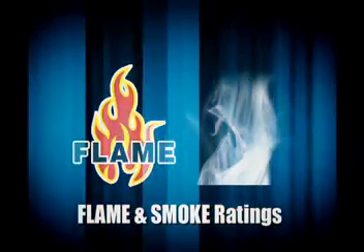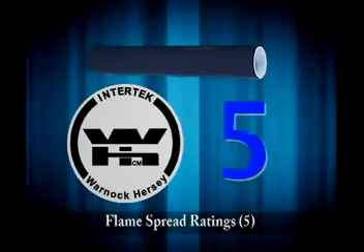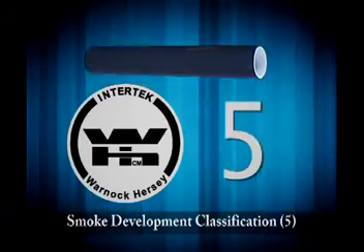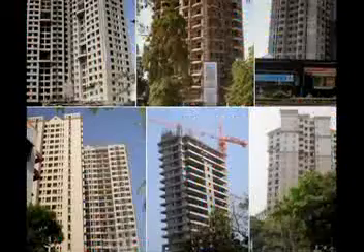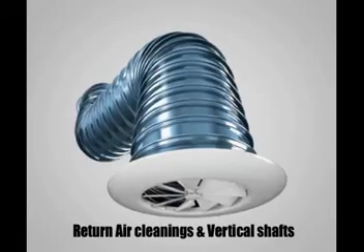Flame and smoke rating. KiTEC pipe has a flame spread of 5 and a smoke development of 5 as per ULC S102.2. The ratings meet most building code requirements, allowing for the use of KiTEC in high-rise construction as well as in return air plenums and vertical shafts.